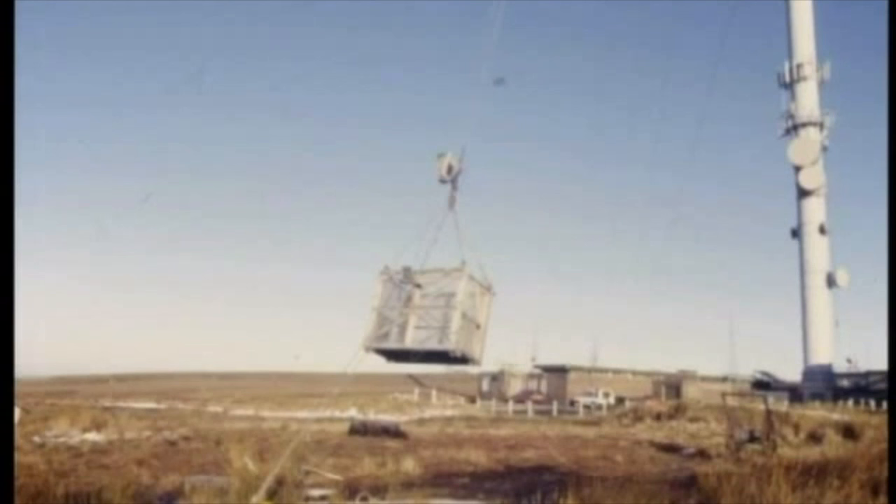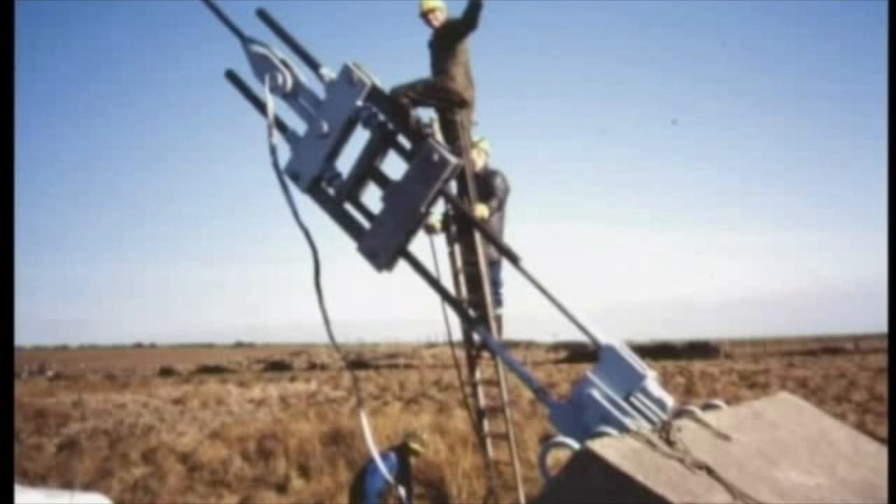Getting outside now: the mast itself requires a great deal of maintenance. Mast verticality and stay tensions are checked regularly. Stays are greased every few years and the mast is painted in a similar cycle. The mast must be vertical within one inch in still air conditions, and stay tensions must remain within close limits of the design value, with any variations requiring thorough investigation. This slide shows the cage which can take four men up to any required height — much easier than climbing the ladder. Here we see the stay tensioning in progress: Jim Doherty waving from the top, Benny Gilroy on the ladder behind him, and Jim's brother Charlie Doherty concentrating on the pressure gauge which indicates the tension in the stay. This operation must be done in a wind speed not exceeding four miles per hour to get valid results.